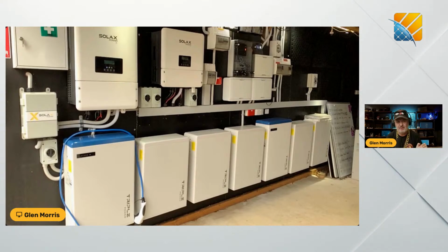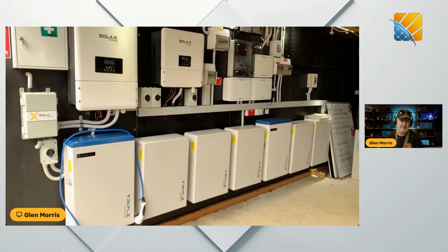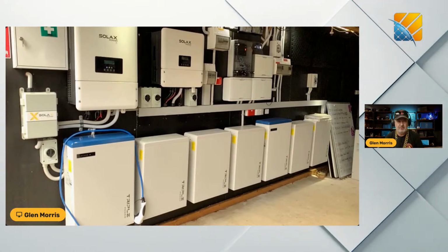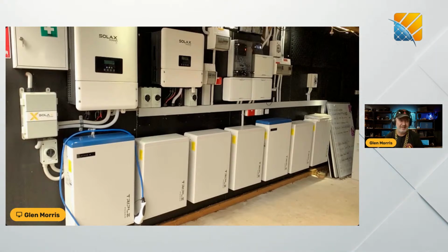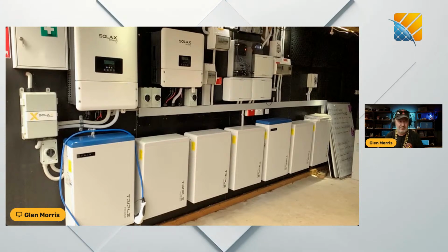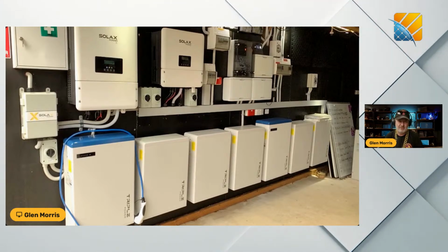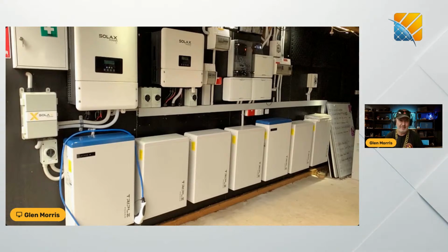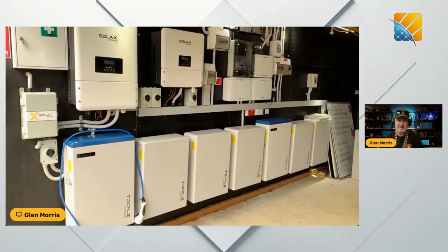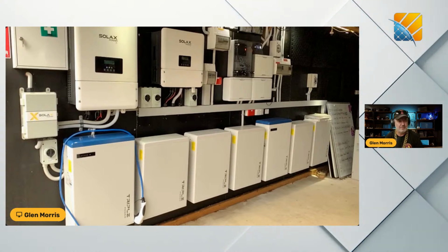So these batteries are 100 volts each, and they're connected in series to get the appropriate voltage for the inverters. The 3-phase inverter goes between 300 and 400 volts, so either 3 or 4 battery modules, and the single-phase inverter, either 2 or 3 battery modules, so 200 to 300 volts on the battery side. Now, you might think, gee, that's a pretty high voltage battery. There's a lot of pluses now with high voltage batteries, which is small cables, longer cable runs, mechanical protection is easier, and the cost of your isolators and overcurrent protection devices is much lower. You're not switching hundreds of amps, you're switching tens of amps. So this 10 kilowatt inverter only draws like 25 amps. It makes it very easy to wire them up. It's a bit like just a solar system, really, but it's a battery in terms of cabling.